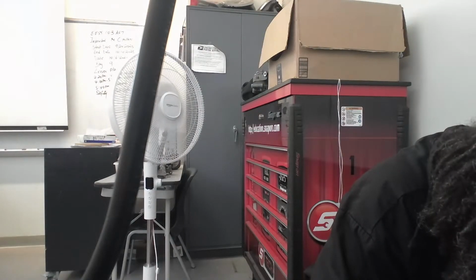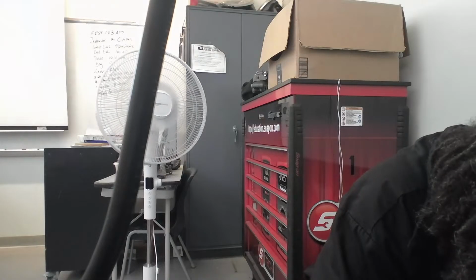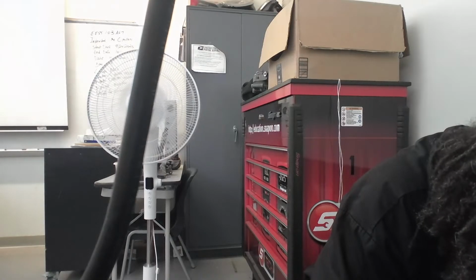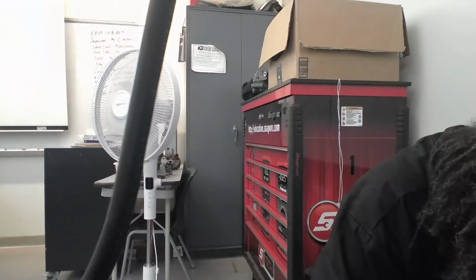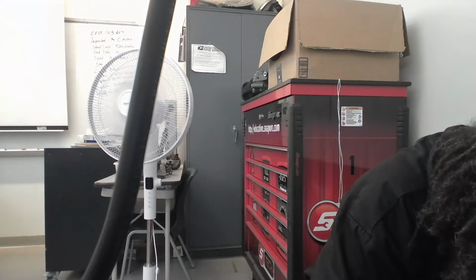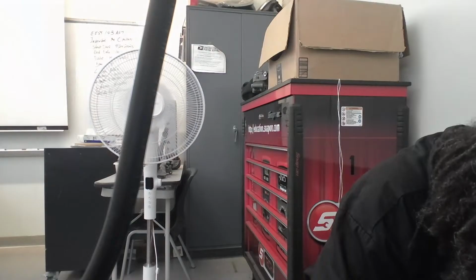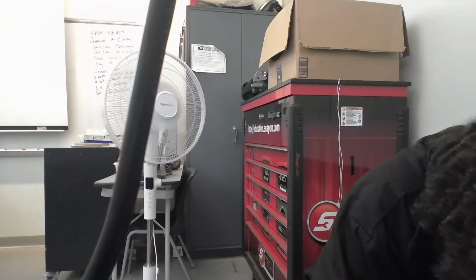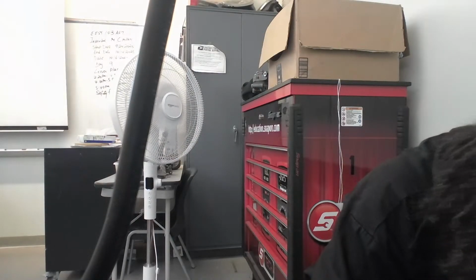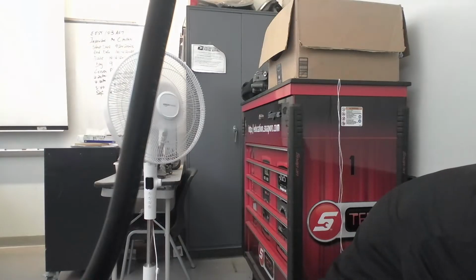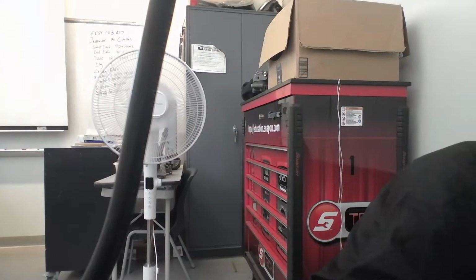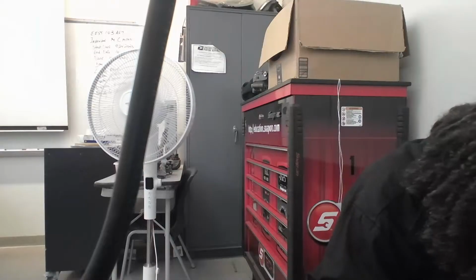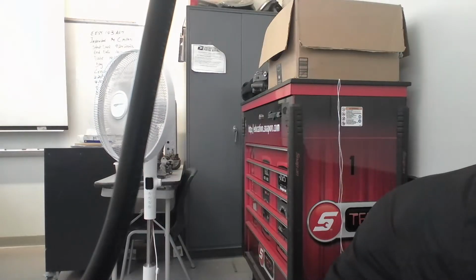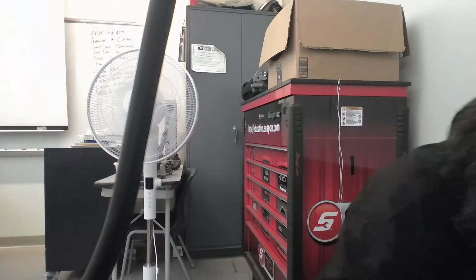Look at section 2.2.1, table 3, on page 12. Underline and highlight every single one of those: Class 00, beige tag, 500 volts. Class 0, red tag, 1,000 volts, and so on all the way to Class 4, orange tag, 3,600 volts to 36,000 volts.